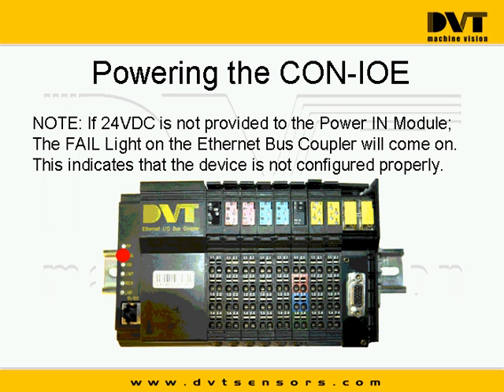Some other areas that you want to focus in on. Well, let me show you. When you supply power to this particular module, you want to keep your eye on a couple of other places. I'll try to highlight those for you. You want to keep your eye on this area right over here, because there should be 3 LEDs lit when this is working properly. One is for the source power, one is for main power, and one is for logic power, telling you that all of those components are properly powered. And if those are all properly powered, that's all set. That'll tell you right there.